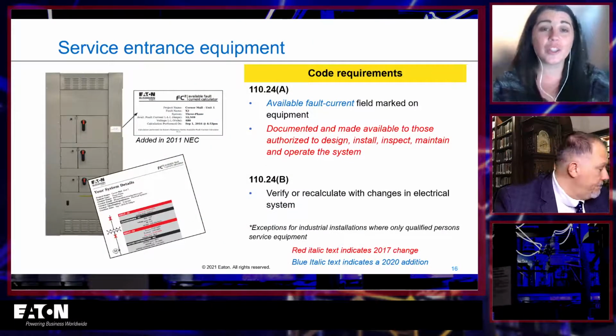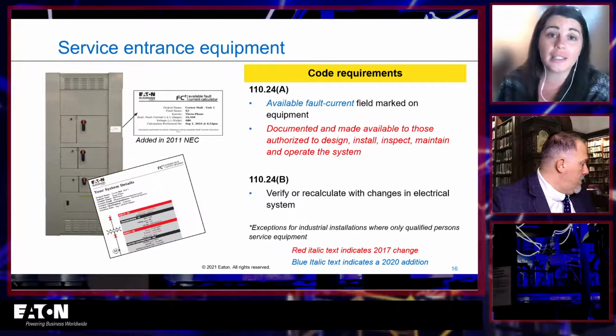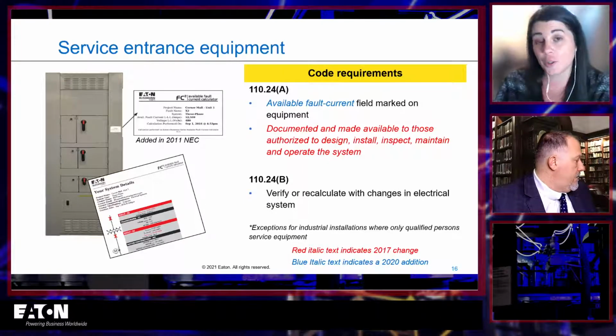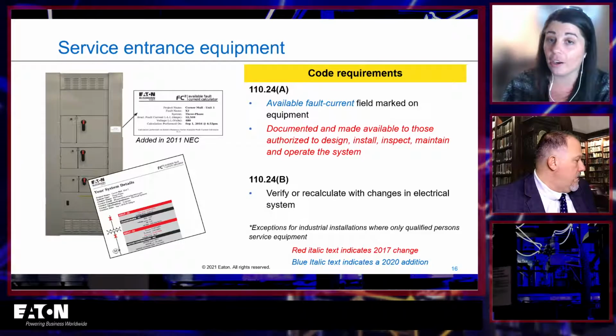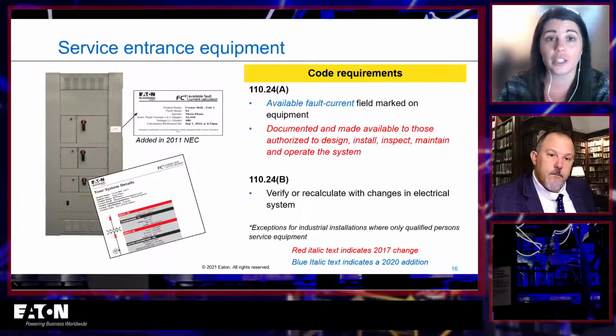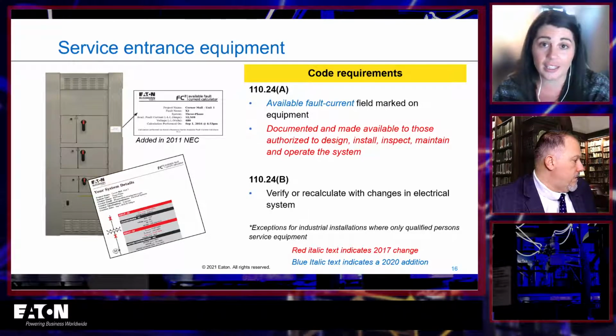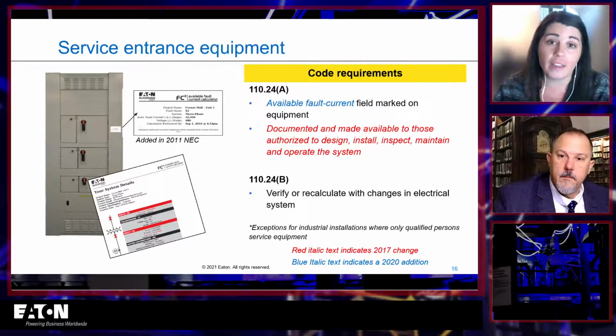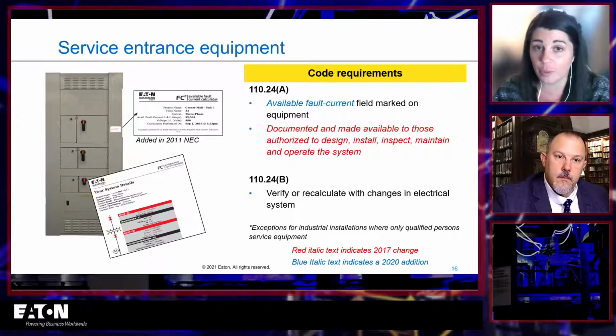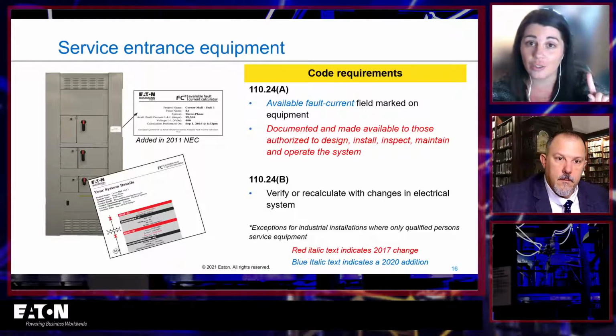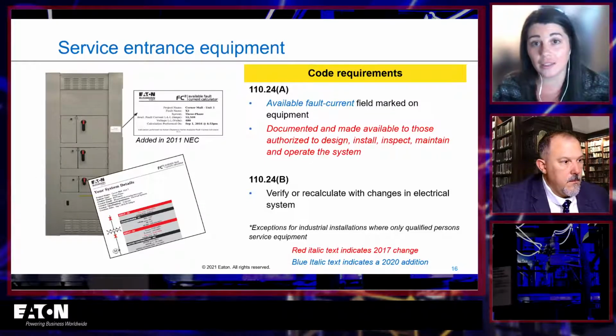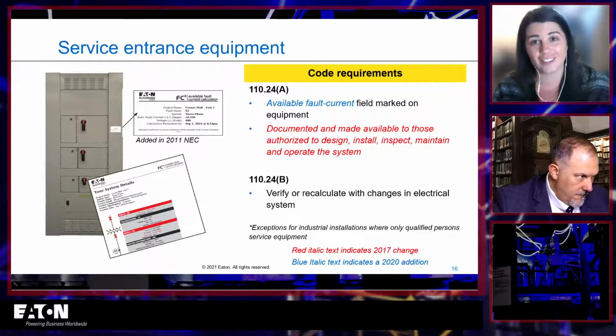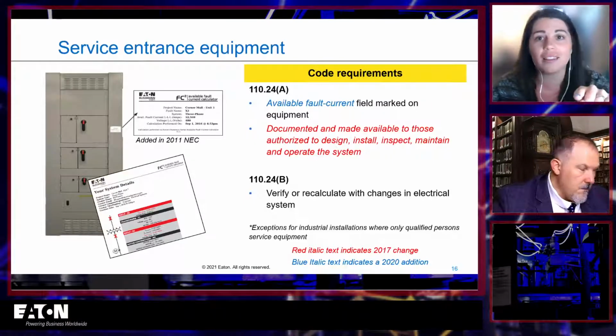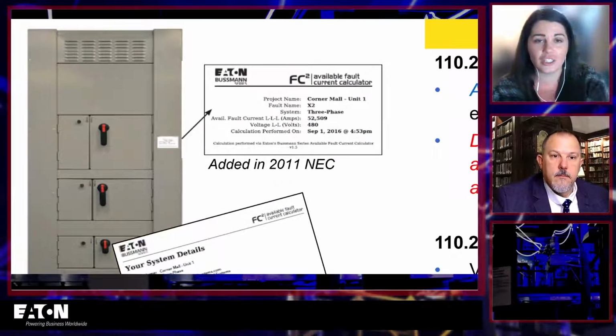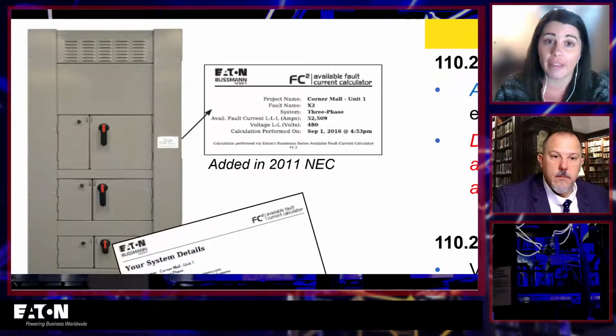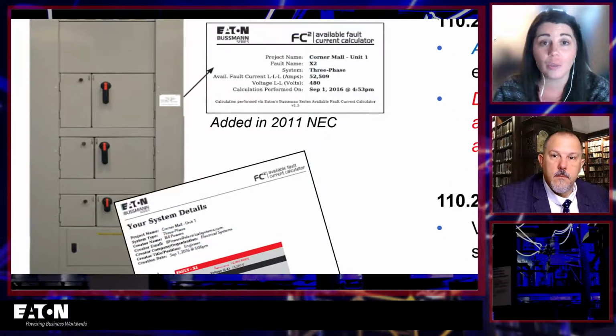Yep. So the first thing we'll talk about is service entrance equipment. This is really the first one that ever got a requirement for available fault current. In 2011, the NEC added a requirement that the available fault current should be field marked on the equipment. Now, they probably didn't use the term available fault current, because only this year is it a consistent use of that term. So you'll see in a lot of these, the blue italic 2020 changes are going to be just the words available fault current. But yeah, you had a field mark.